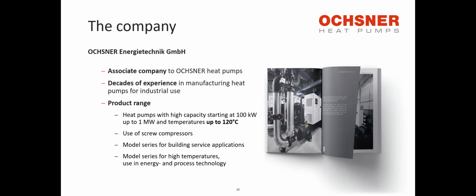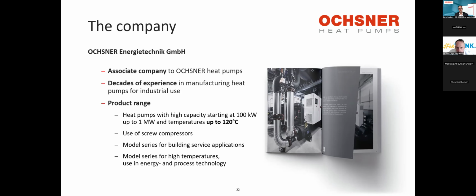We are working with screw compressors and shell and tube heat exchangers because they are more robust in these systems, because we're talking about life cycles or running times of a heat pump. A standard heat pump in a household has a running time of about 1,800 to 2,200 operating hours a year. We in the process area are talking of 6,000 to 8,000 operating hours per year, where we need to have very high efficiency and also robustness for all these parts in the system, and therefore we are looking for screw compressors and shell and tube heat exchangers to have these robust systems.